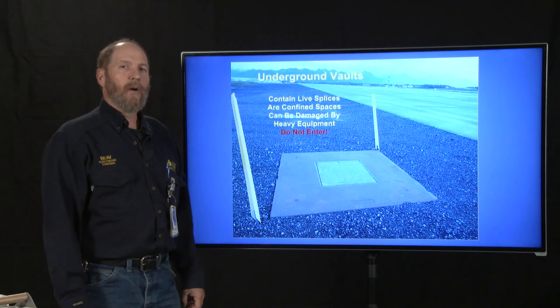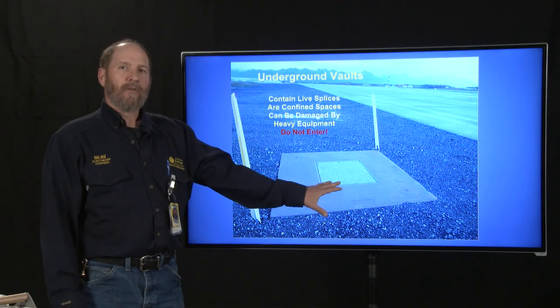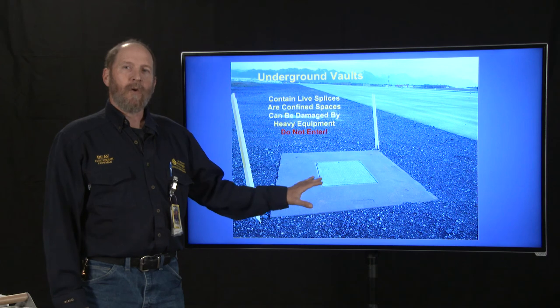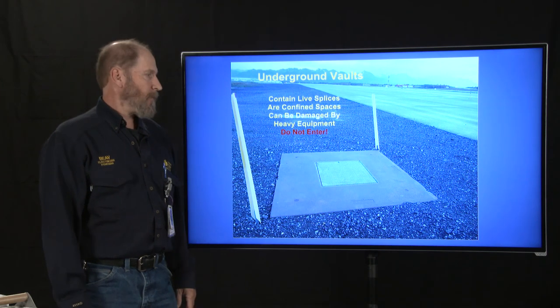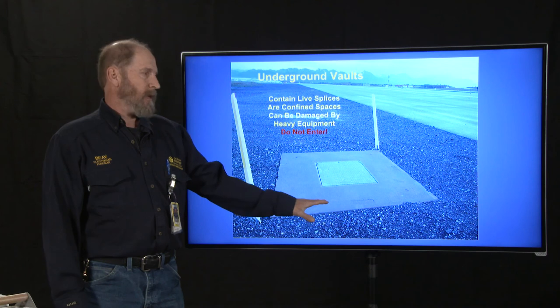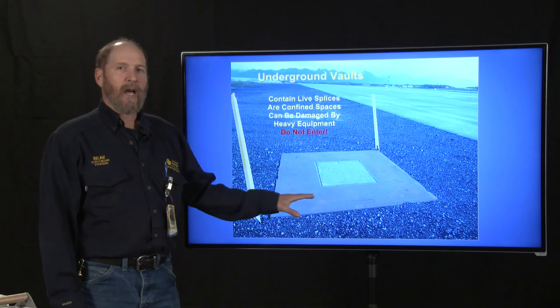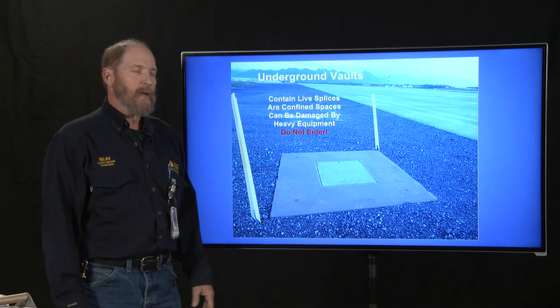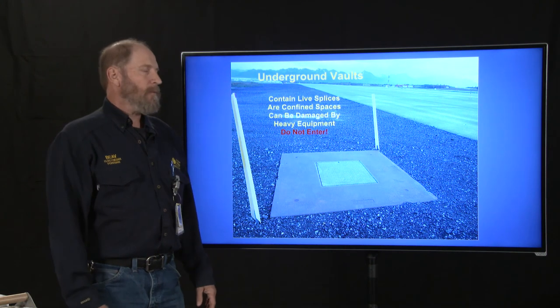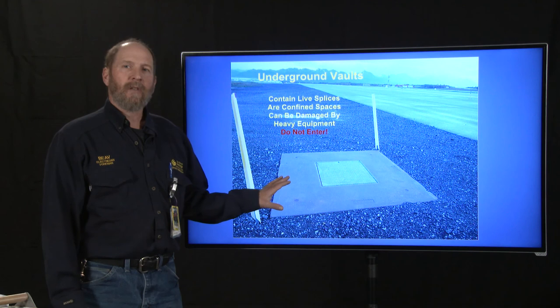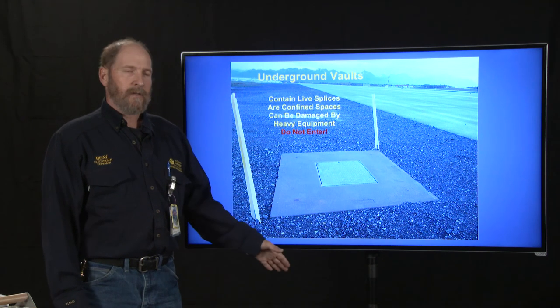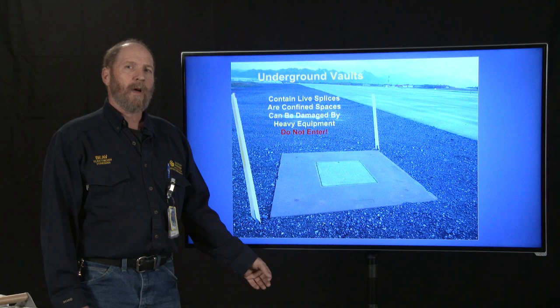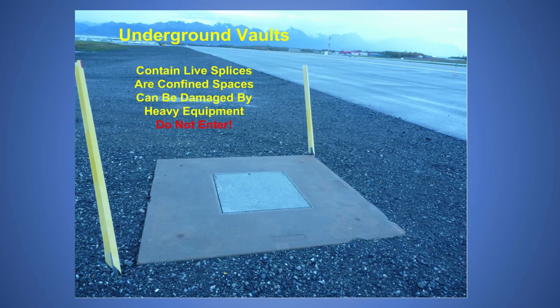Okay, from our airfield lighting vault, we go out into concrete vaults out on the airfield. This might not be the exact same way on your airfield, but this is the way it is at Anchorage. Now, these lighting vaults are about 8 feet deep. And they have a lot of live splices or a lot of wires that come into them. They're extremely dangerous. Before we go into them, we'll lock out the entire airfield. We'll send a sniffer down there to make sure the oxygen levels are correct. Then we'll check for any voltage in there, and then we will go down in. So if you don't know exactly what you're doing, you need to stay out of these lighting vaults.